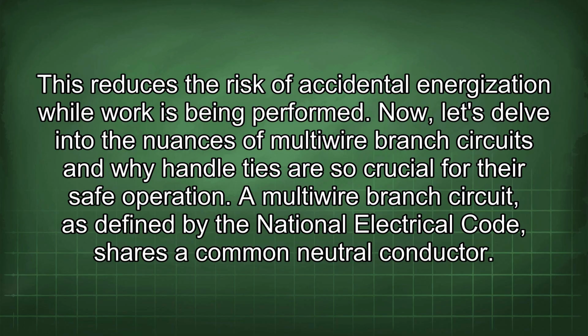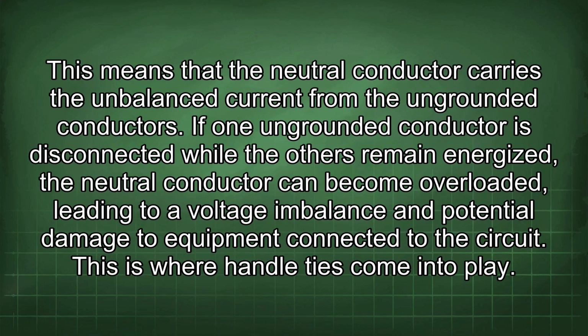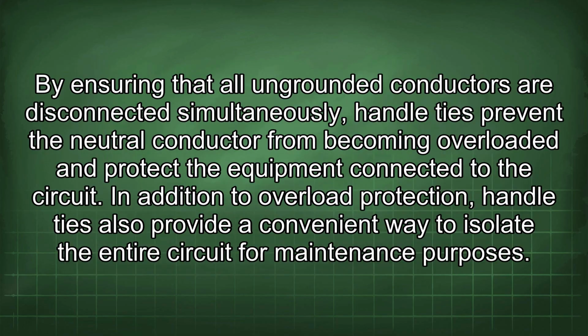Now let's delve into the nuances of multi-wire branch circuits and why handle ties are so crucial for the safe operation. A multi-wire branch circuit, as defined by the National Electrical Code, shares a common neutral conductor. This means that the neutral conductor carries the unbalanced current from the ungrounded conductors. If one ungrounded conductor is disconnected while the others remain energized, the neutral conductor can become overloaded, leading to a voltage imbalance and potential damage to equipment connected to the circuit. This is where handle ties come into play. By ensuring that all ungrounded conductors are disconnected simultaneously, handle ties prevent the neutral conductor from becoming overloaded and protect the equipment connected to the circuit.